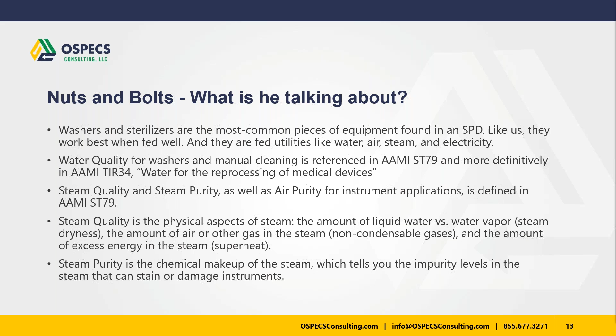So if you've got bad water quality or bad steam purity, you're going to stain the instruments, you're going to corrode the instruments, you're going to decrease their life. They're going to have to go out for repair more often. Cost of ownership goes up. Availability of instruments for the things they're there for goes down. Bad steam quality means wet loads. Guess what? You liked it the first time, you're going to get to really like it the second time that you process it. Failed sterilization, less than sterility assurance level.